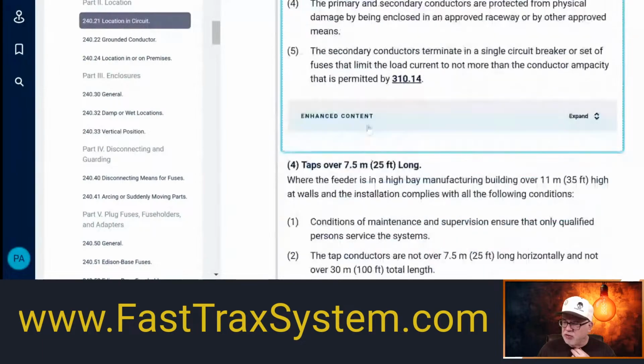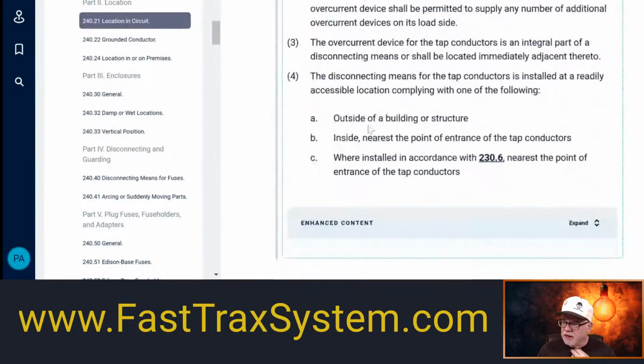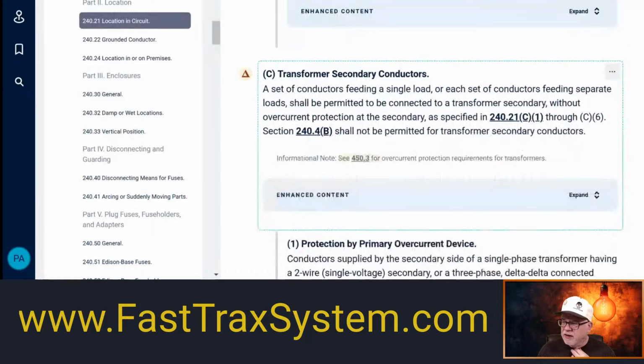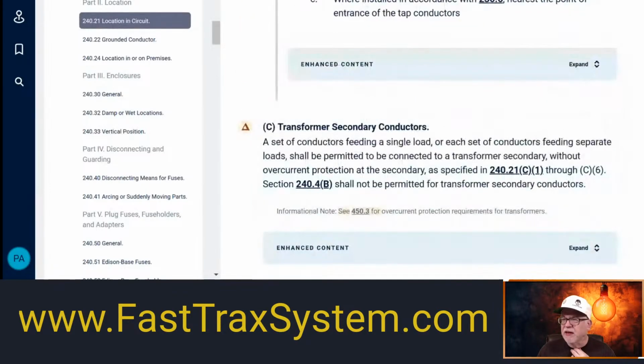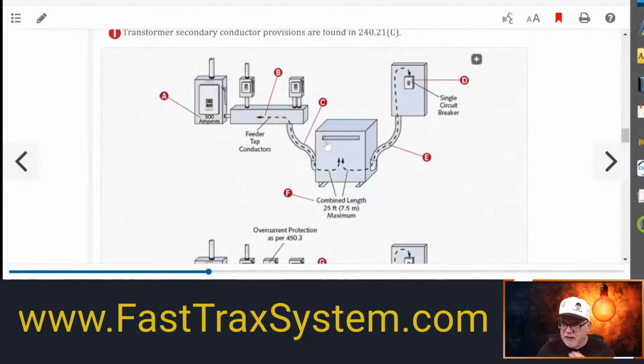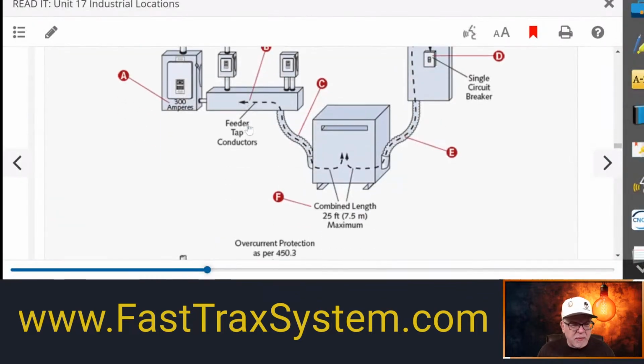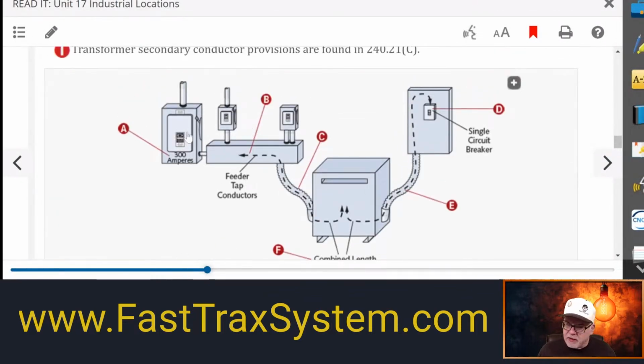Okay, so if I showed you the example, and let's go here. Hold on here. Let's see. Oh. No, I got to take you back to my example. Let me show you my example right here. So this is what we're talking about right here. See? So this right here, so people aren't confused, this is a panel. This is feeding multiple loads. Okay? And I can blow this up a little bit if it's hard to see. That a little better? This panel is feeding this trough, which is feeding multiple loads. So it's a feeder. And they're tapping onto it here to feed this transformer. This is a feeder tap.